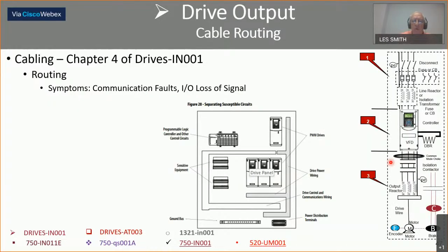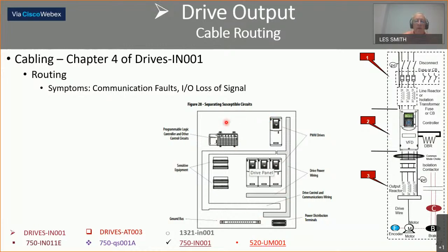Regarding routing: keep all your low-voltage wiring on one side of the panel and your high-voltage or high-power wiring on the other side. If your conduits come in, your ground currents will travel on one side of the panel — you don't want the ground currents traveling to the other side. Without proper grounding, the back plate will pick up the ground current, which can get into the PLC and sensitive instruments.